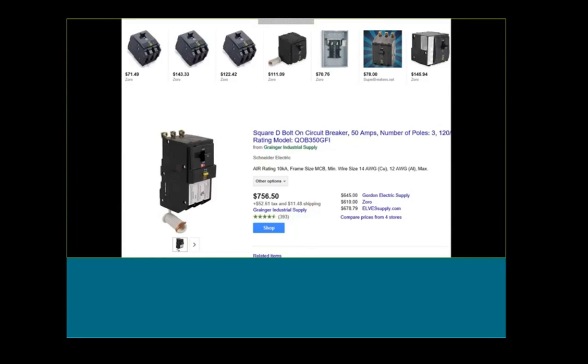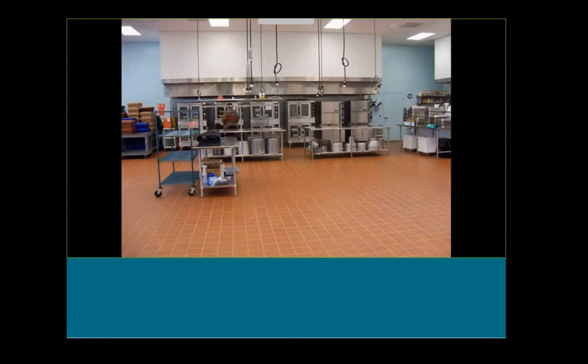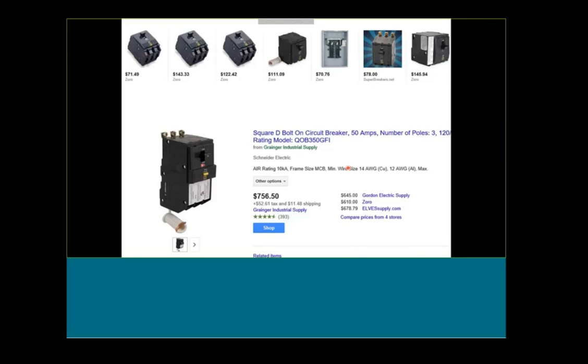In the 2014 code, that breaker — I just Googled and checked prices — would cost anywhere from 70 to 150 bucks. The GFCI version of that breaker costs 750, so it's anywhere from 5 to 10 times the price of the standard circuit breaker. That's significant when you factor in all four pieces of equipment plus the dangling cords — we've got several thousand dollars worth of code change right in that photograph.